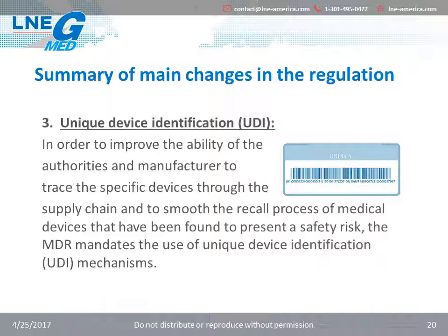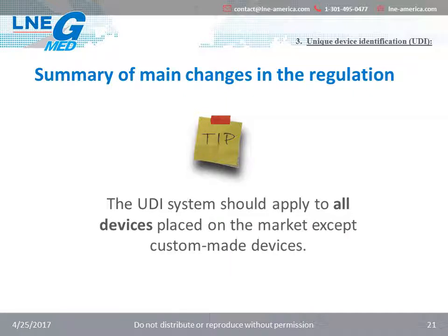It should also help to reduce medical errors and to fight against falsified devices. Use of the UDI system should also improve purchasing and waste disposal policies and stock management by health institutions and other economic operators, and where possible be compatible with other authentication systems already in place in those settings. There is a very important tip in this slide. The UDI system should apply to all devices placed on the market except custom-made devices.